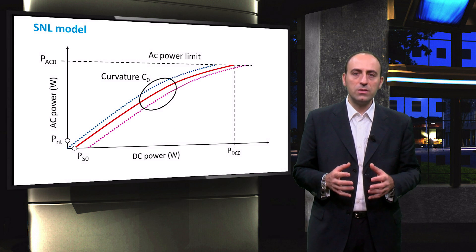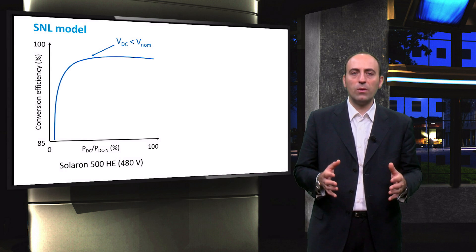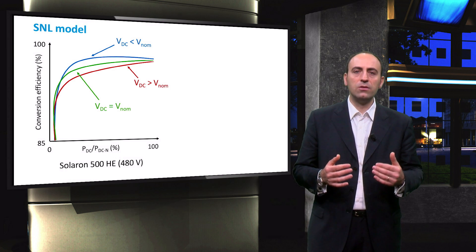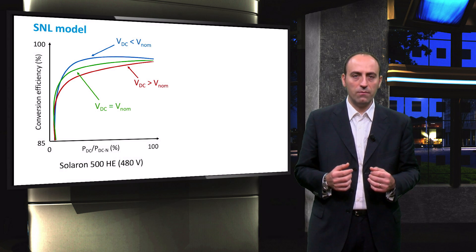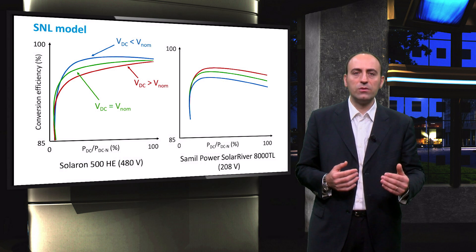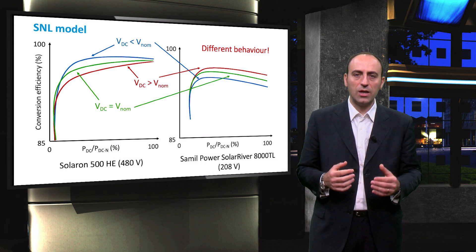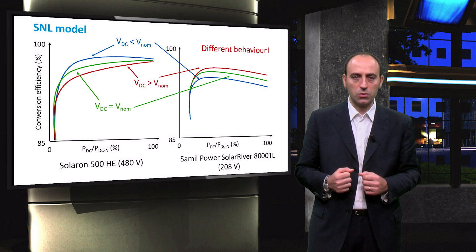The dependency of the inverter efficiency on the DC input voltage is a very complex phenomenon. For a given inverter, there is a different behavior when the DC voltage is lower, equal, or higher than the nominal voltage of the inverter. Nevertheless, for a different type of inverter, a higher voltage can lead to higher efficiencies, or vice versa. The differences between the different inverter types can be partially explained by the different types of switches used.